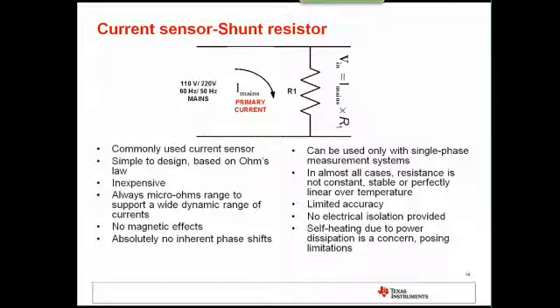So there are multiple types of current sensors that are used. Shunt is one commonly used sensor. It's based off of Ohm's law. Basically, the voltage that's fed to the analog to digital converter is equal to the current drawn by the load, multiplied by the resistance of the shunt resistor. One advantage is that this is a very inexpensive solution. And since you have a relatively large current and a small maximum voltage that the ADC can sense, you have the shunt resistor always in the range of micro-ohms.